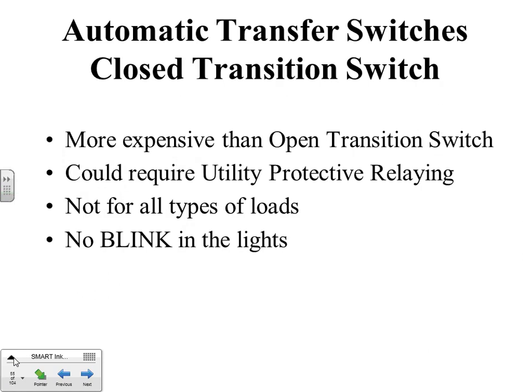All right. Closed transition switch. This is a little more expensive than the open transition, and I will change this from could to will require utility protective relaying. Especially Xcel is very interested in seeing that, because we're actually paralleling with their grid. They're very particular about anybody paralleling with their stuff. It's not for all types of loads, and you will not see a blink in the lights when it goes back to normal after an outage.